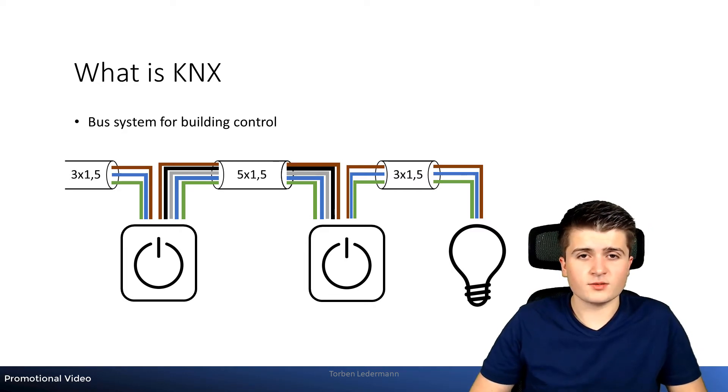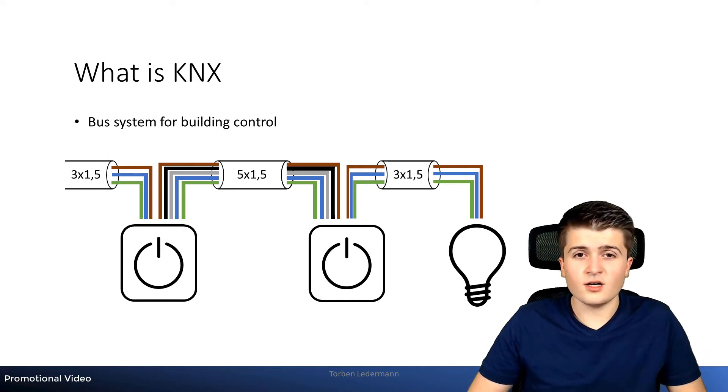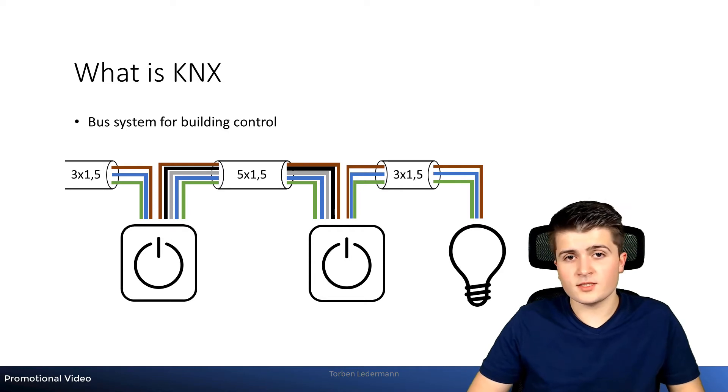But why the effort to use such KNX components? Well, therefore we have to take a look at the conventional installation. So here in this example you can see two switches and a light, a changeover circuit. And you can also see the necessary cables. So to the first switch we need three wires, to the second switch five wires, and to the light itself we also need three wires. So a lot of cable that we need in order to make the circuit work. And even then, higher level functions such as timers or central functions can only be implemented to a limited extent.